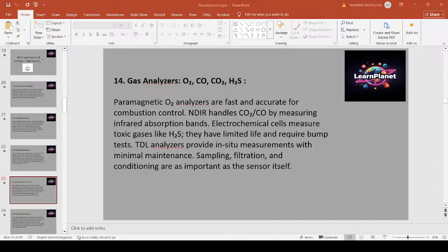So the paramagnetic oxygen analyzers are good for combustion control with fast response, and NDIR is the standard for CO2, CO due to selective IR absorption. Electrochemical cells are compact for toxic gases like H2S, but have finite lifetime and require bump tests. Tunable diode laser, TDL analyzers, provide highly selective in situ measurements for difficult species. Sampling systems, filters, heated lines, and calibration gas manifolds are as critical as the sensor for reliable readings. Example, for flare gas monitoring, install an NDIR for CO2, CO, and a separate IS protected electrochemical H2S cell with periodic bump test.